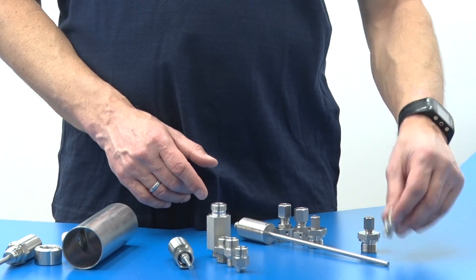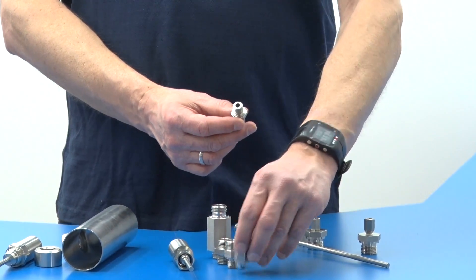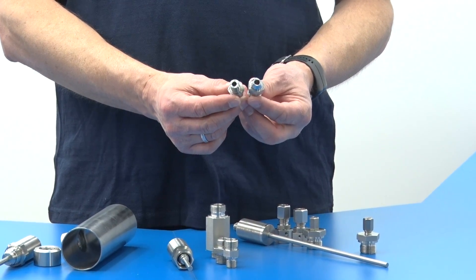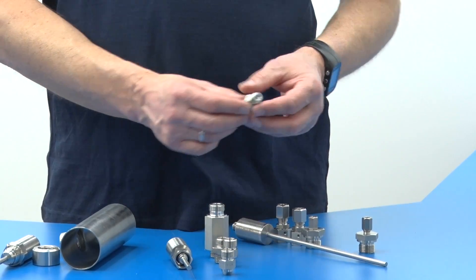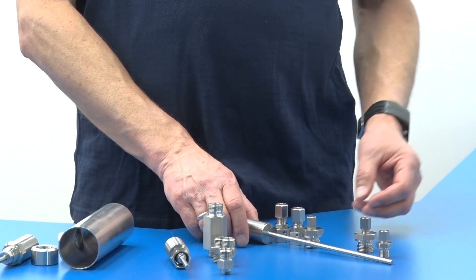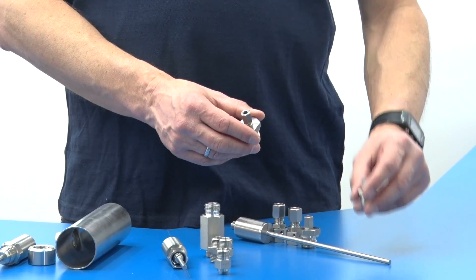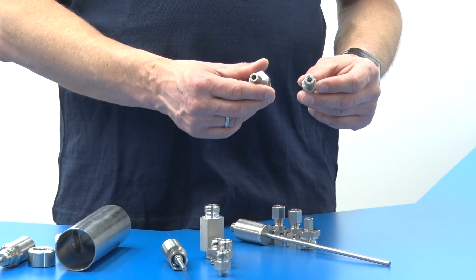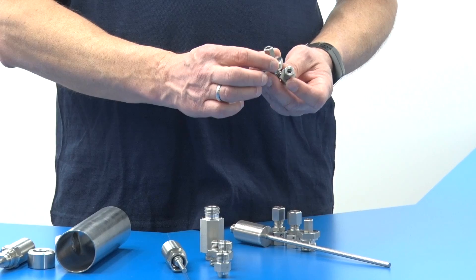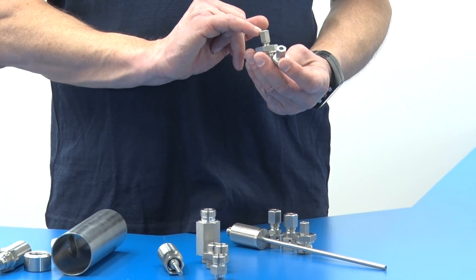Basically, the sensor can be welded or screwed. With PTFE olives, the connection is safe up to 6-bar, while metal olives endure up to 100-bar.